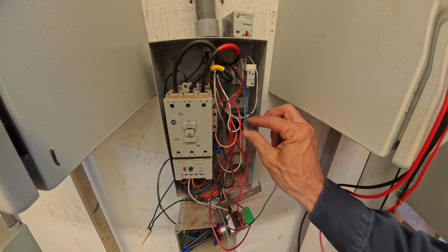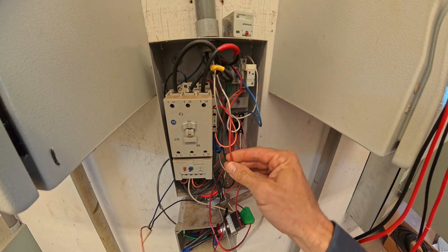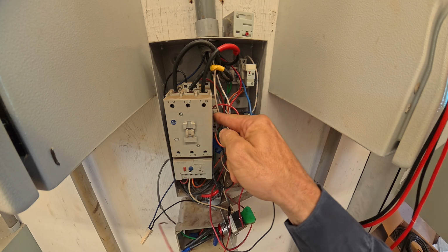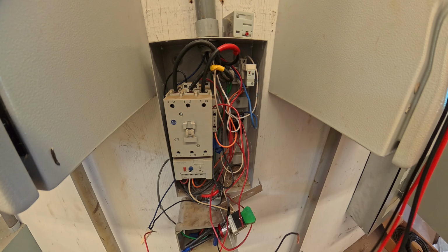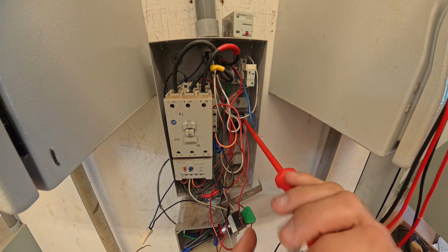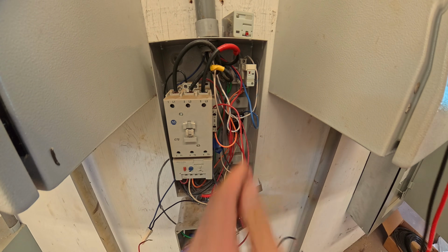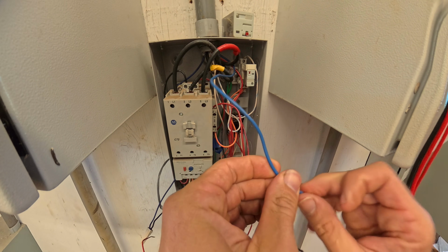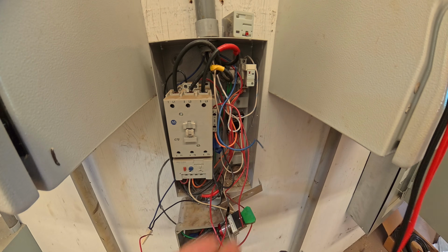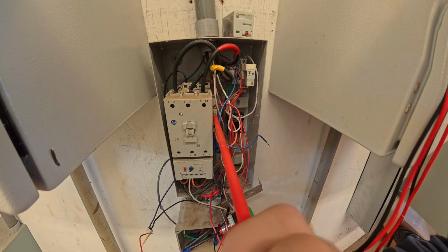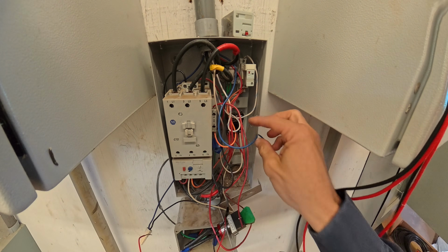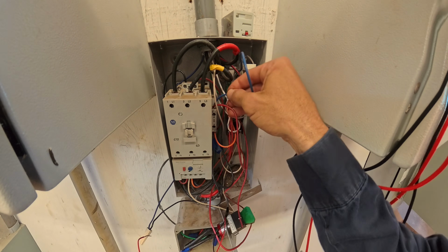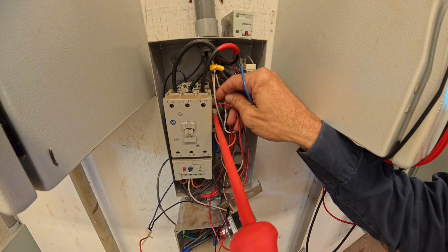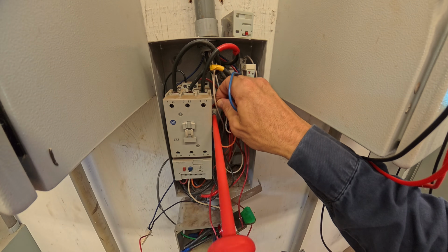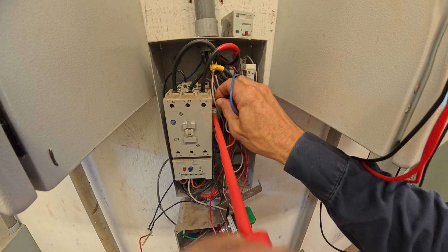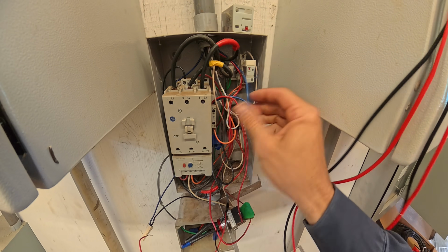So currently, we just need to take this wire and put it onto a wire that is always hot, which is this guy right here. And then we'll always have 120 on the other end at the beginning of our rung. I can just back him off. Basically, I'm taking the float, there we go, I'm taking the float completely out of the hardwired series wiring of this motor contactor's coil.